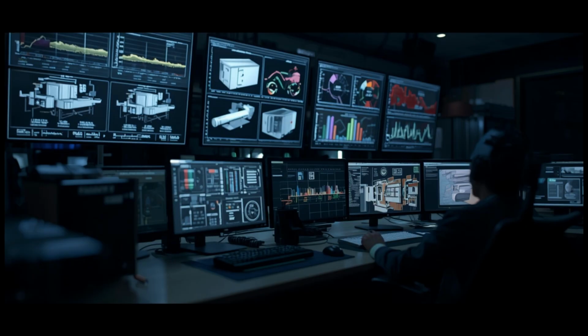Beyond these moment-to-moment corrections, the system also maintains a quieter, longer memory of everything it observes. This process, known as trending, involves recording countless readings over time, building a slow, detailed record of how conditions have shifted across the hours, the days, and eventually the seasons. A facilities operator, seated at a desk in the building or monitoring remotely from elsewhere, can call up this recorded history on a graphical display, watching a smooth line trace the rise and fall of a room's temperature over the previous day, or comparing how closely a fan's actual speed has tracked its intended target over the past several hours.